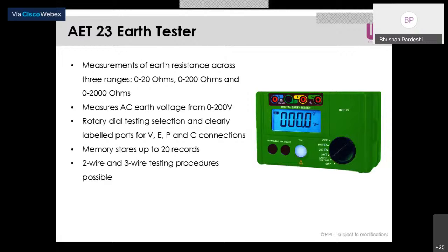So this is the advantage of giving the extra voltage measurement in the earth testers. It also measures the earth voltage, from 0 to 200 volt. The range we have given is 0 to 200 volt, but basically that much voltage is not required for measuring the voltage in earthing. But this is the extra voltage, it acts like a multimeter also. It will measure your earth voltage, and your normal voltage greater than 10 volts, up to 200 volts.